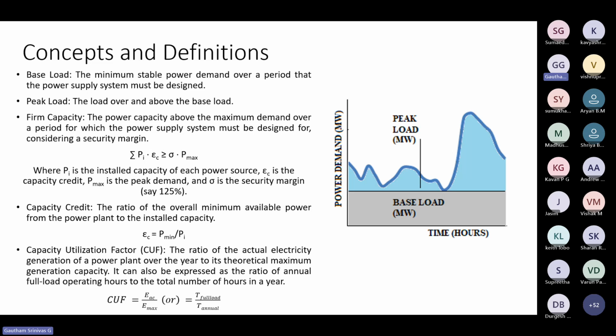You can't do that with coal, so coal can never be used for peak load. Basically, a thermal power plant can never be used for peak load, because the startup itself will take hours or even days to reach that level and reach steady state. So thermal can only be used for base load. For peak load, you can use gas, hydro, or even diesel generators. These are some examples.